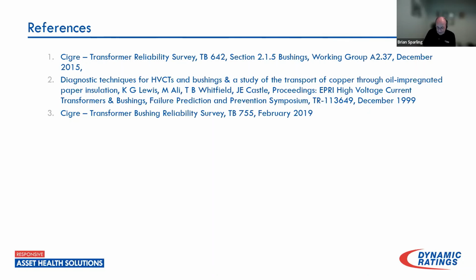These are the things that I have seen, where the standard frequency testing shows you everything looks okay, like that diagram I showed you before. But when doing it at multiple frequencies, it can reveal a whole bunch of other issues. So it's a far more sensitive test, and just don't go by the fundamental frequency test when you're doing it. Okay. Next question. Is there a certain level for percentage power factor which could be considered as an alert, or is the most important the trend of change over time?